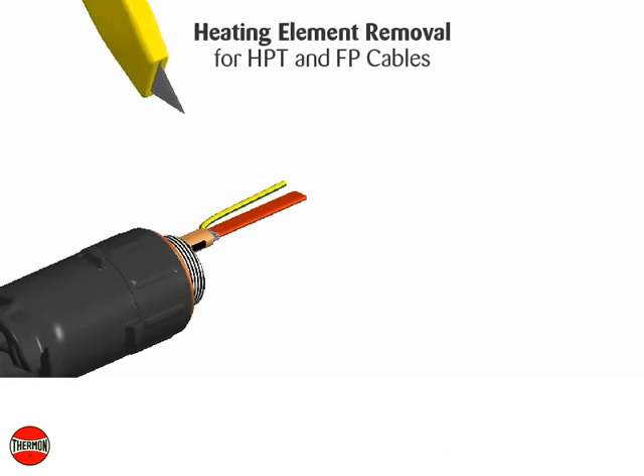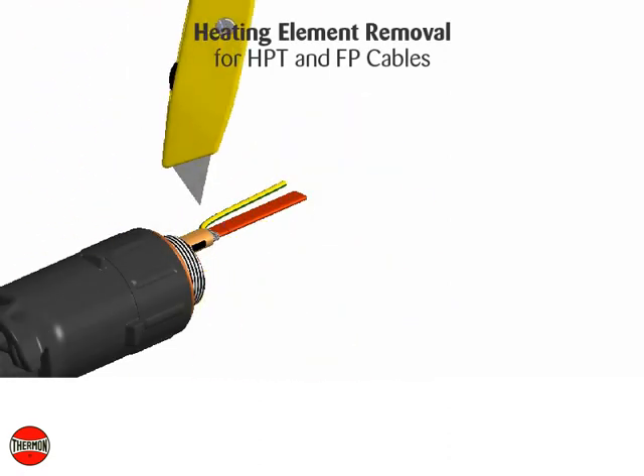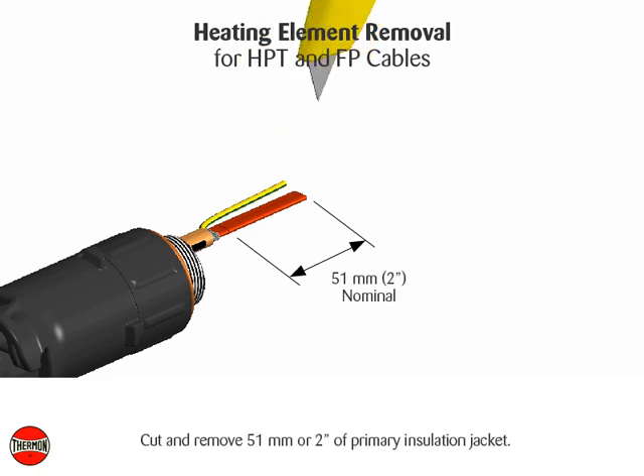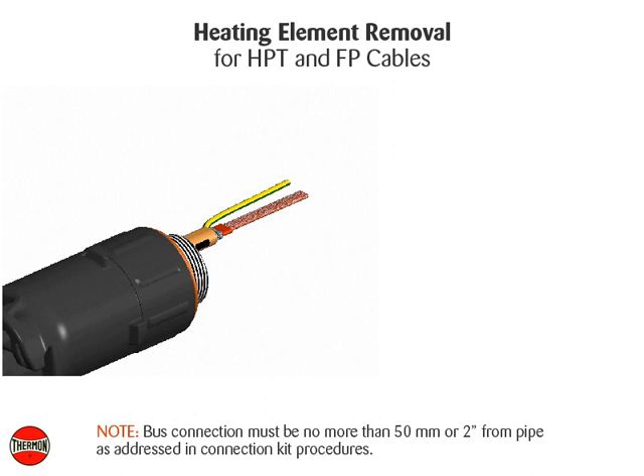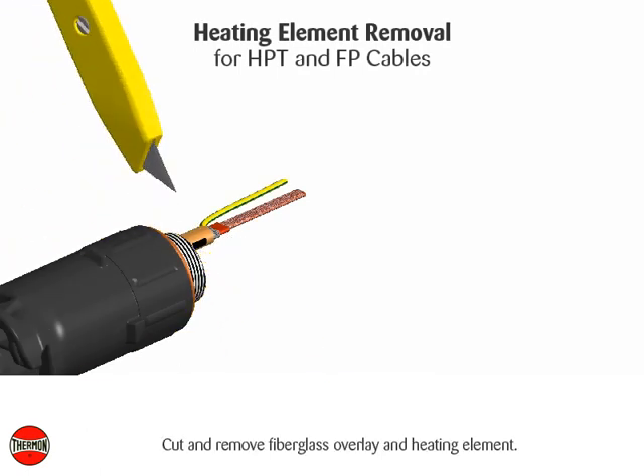Heating element removal for HPT and FP cables: cut and remove 51 millimeters (2 inches) of primary insulation jacket. Note: bus connection must be no more than 50 millimeters (2 inches) from pipe, as addressed in connection kit procedures. Cut and remove fiberglass overlay and heating element.